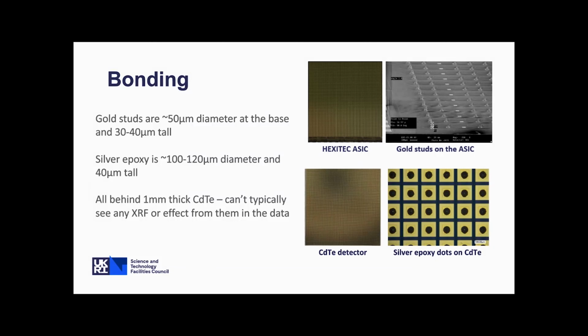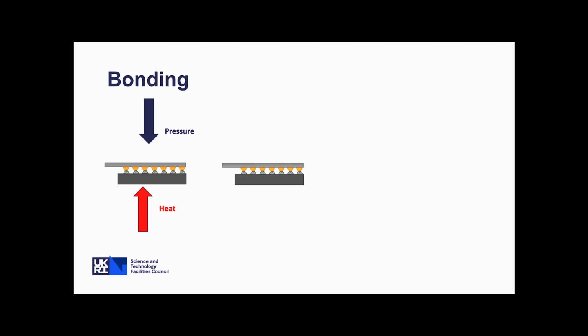So when we have these two devices, we've got the gold studs on the ASIC on the top, and then we've got the cartoon of the silver epoxy on the detector. We press these together in a flip chip machine. We apply pressure on the top to get that insertion. We heat it in situ, keeping it at a relatively low temperature because the cadmium telluride is quite sensitive to temperature. So we need to keep that below 120 or 150 degrees C.